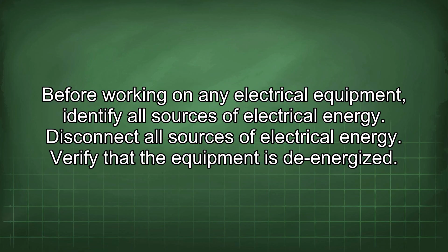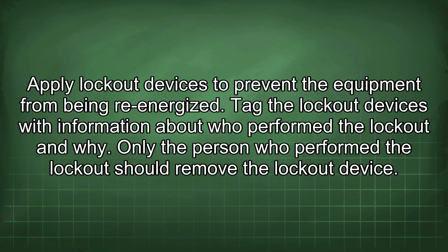Tag the lockout devices with information about who performed the lockout and why. Only the person who performed the lockout should remove the lockout device. Follow a documented lockout/tagout procedure.